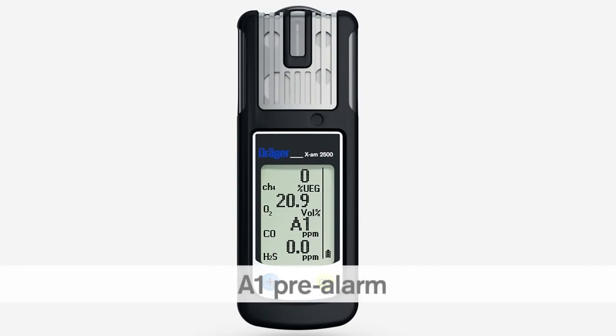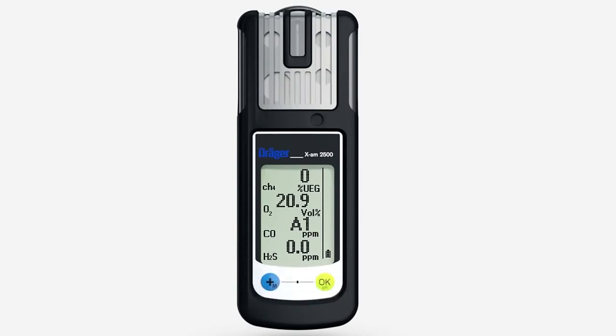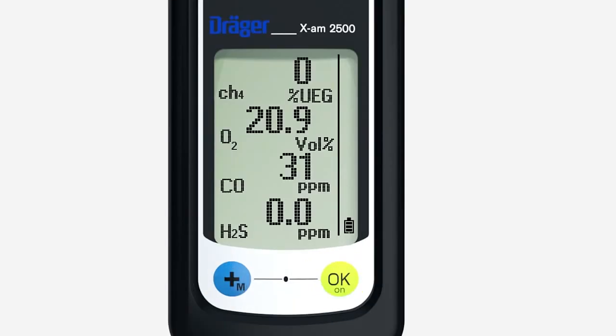We'll start with the A1 pre-warning threshold. The alarm threshold can be changed by using the CC Vision computer software, which is available free of charge on the product page of the XAM 2500 on the Dräger homepage www.dräger.com. The A1 alarm sounds if the concentration is higher than normal but doesn't yet constitute an acute hazard. The audible, visual and vibration alarms are all activated periodically. A1 alternates in the display with the gas concentration. An A1 alarm can be acknowledged by pressing the OK key. The alarm automatically stops as soon as the concentration drops below the defined threshold.